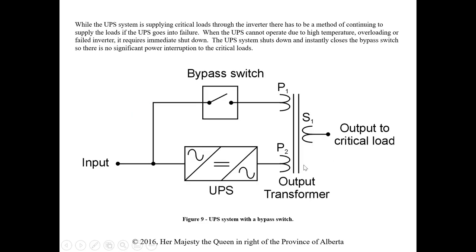There must always be a method of continuing to supply loads if the UPS goes into failure. UPS systems have electronic components that could fail at any time. When the UPS cannot be operated due to high temperature, overloading, or a failed inverter, it requires immediate shutdown. The UPS system shuts down and instantly closes a bypass switch so there is no significant power interruption to the critical loads.